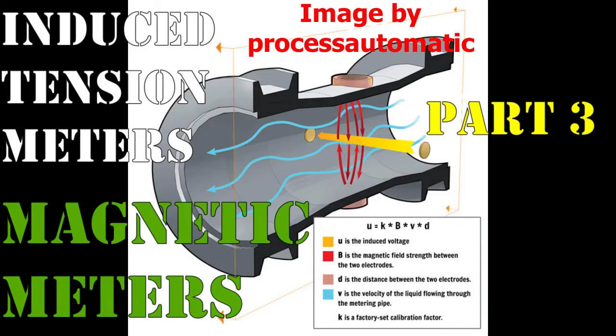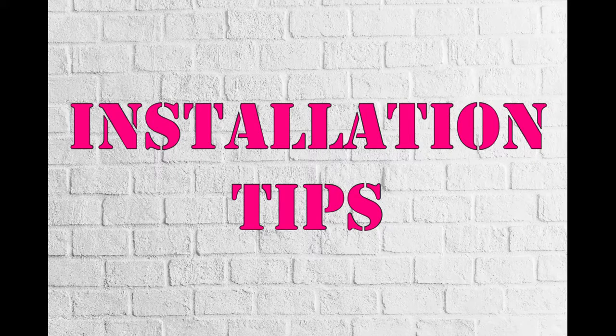Today I'm gonna talk about magnetic flow meters. If the fluid velocity exceeds 2 or 3 meters per second, it is advisable to place a protection diaphragm at the entrance of the element to prevent its erosion, whose internal diameter must be the same as the pipe, and the velocity of the fluid should not be greater than 5 meters per second to prevent wear.